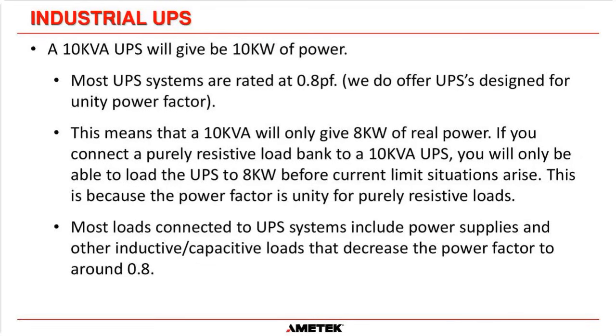And you've got to understand as well that most loads connected to a UPS system have inductance, capacitance, and resistance. So the industry standard is 0.8, although that is changing now because we have power factor corrected power supplies, and the power factor is getting closer to unity on some of these power supplies. But historically, 0.8 power factor is what is required for a UPS.